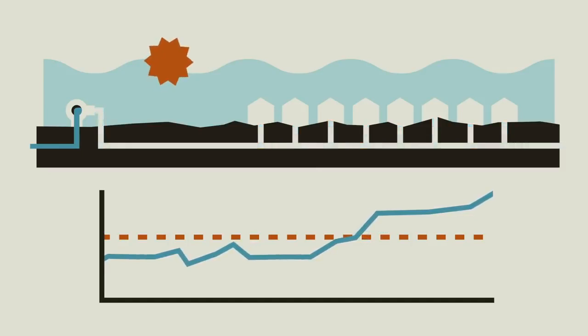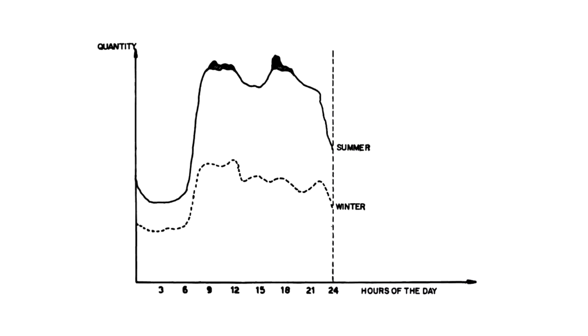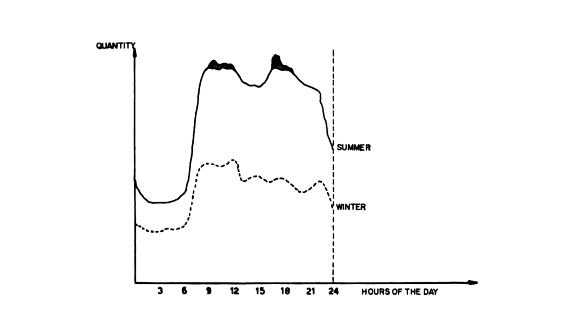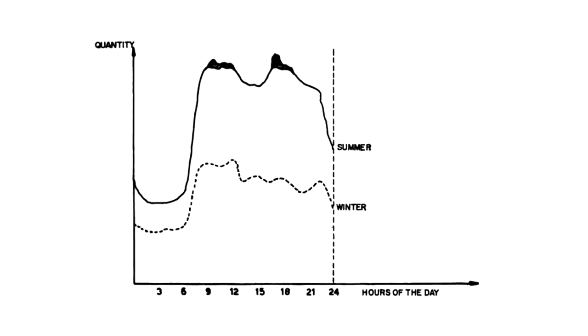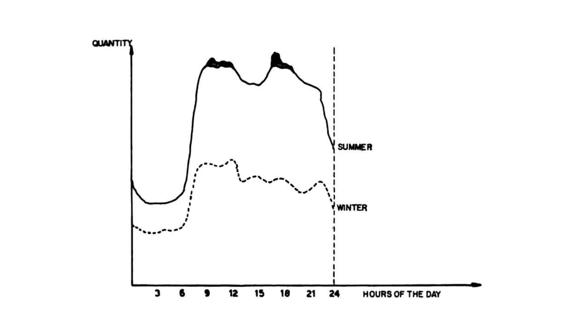Almost right off the bat, your new pump can't meet your system demand because it was only sized for the average. Water demand in large urban areas can vary significantly over the course of a normal day, with the peak hourly demand, usually in the morning or evening, sometimes being as much as 5 times the average daily demand.